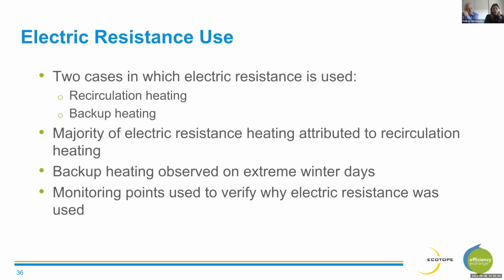The majority of electric resistance heating that we saw at Bayview could be attributed to recirculation heating. We only observed this backup heating on extreme winter days when the system entered defrost mode for the majority of the day. And we can use our monitoring points to verify why the electric resistance turned on. So if we can see that we have adequate hot water storage levels and that the temperature coming out of the primary storage tank is adequately hot, we know that this electric resistance heating is used for recirc.